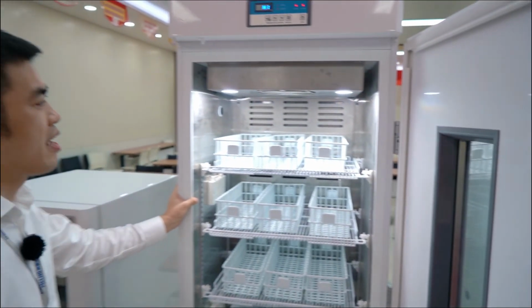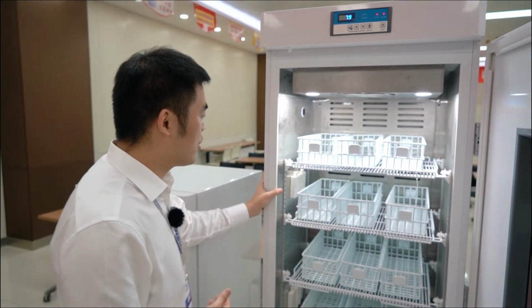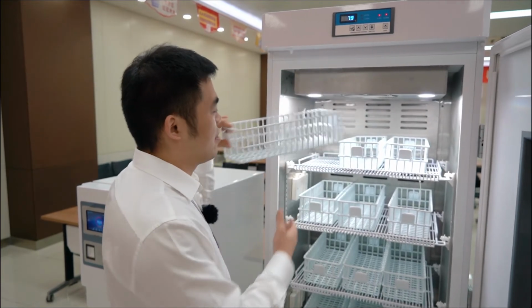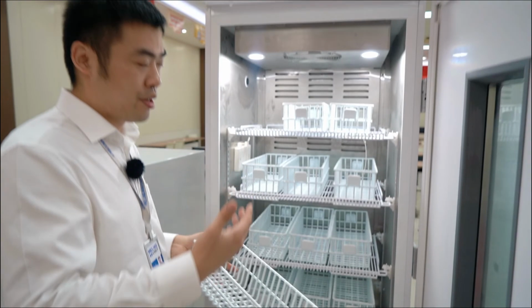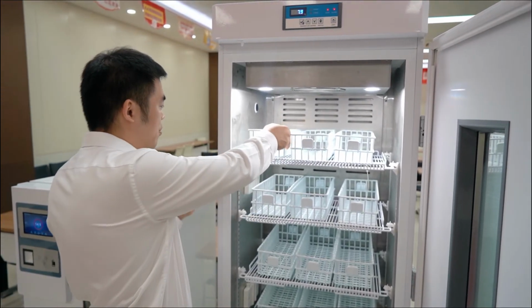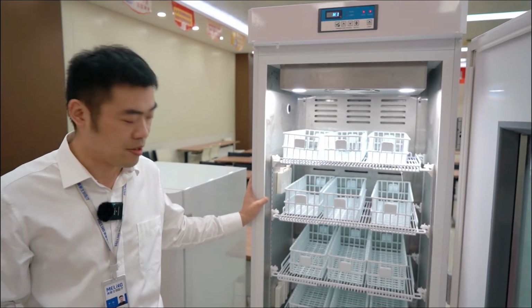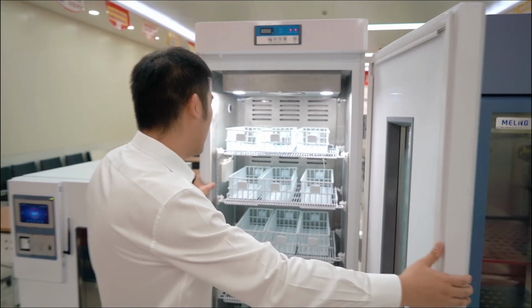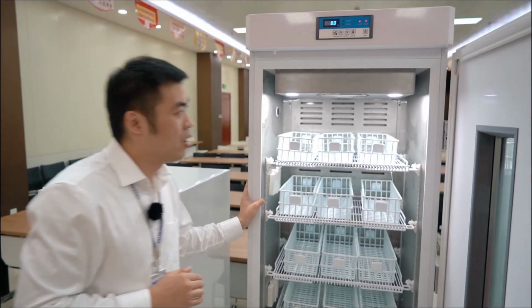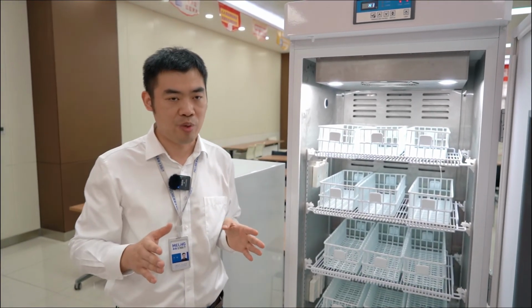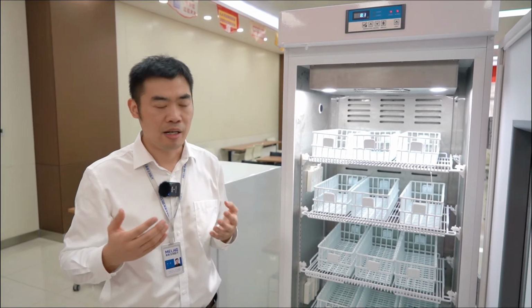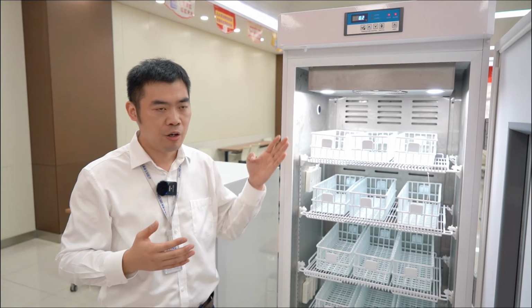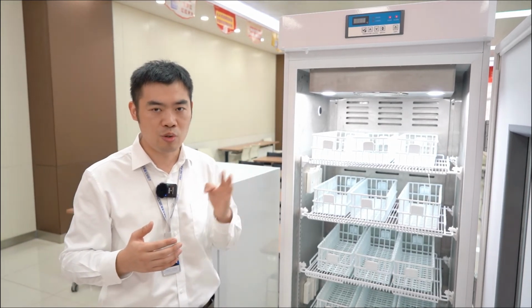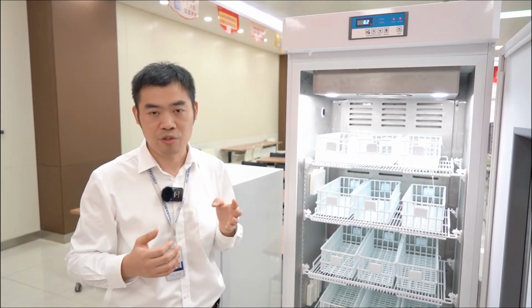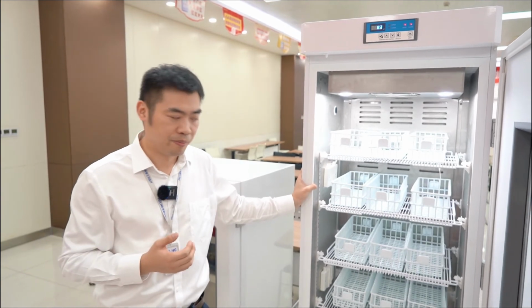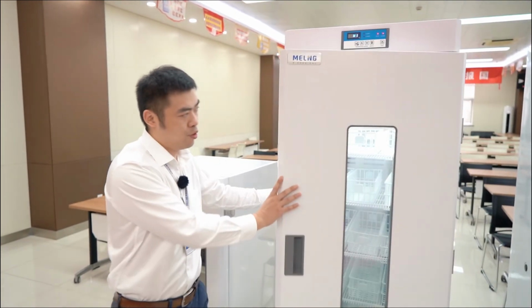Well, the whole interior cabinet is made of stainless steel, and you can choose wall shelves with the blood separator, or you can choose drawers as an option. So we are able to provide different kinds of provisions for customer selection. And most importantly, the temperature. These units conform to the AABB standards, which require all the hot points and the cold points to be within 2 to 6 degrees. That's the mandatory requirement for blood storage. So this unit is completely designed for blood storage.